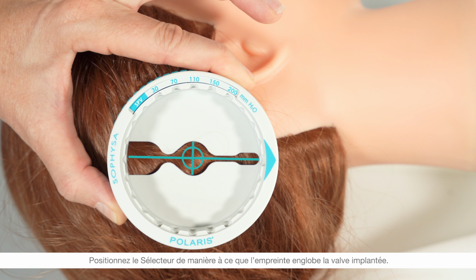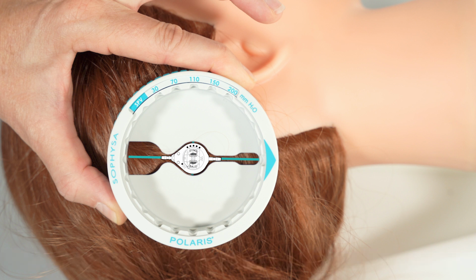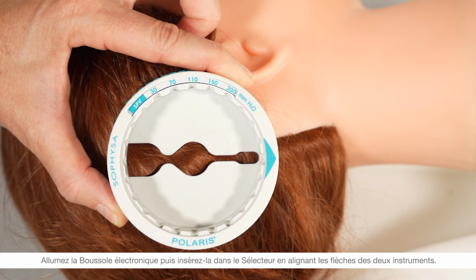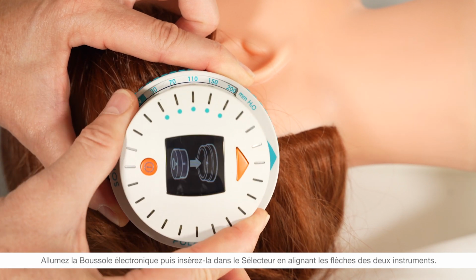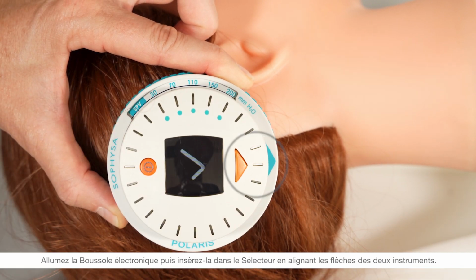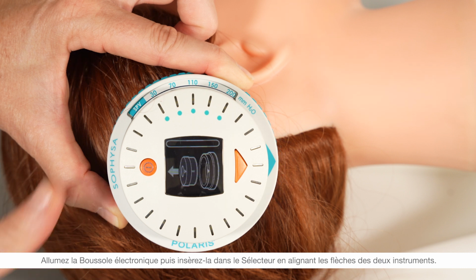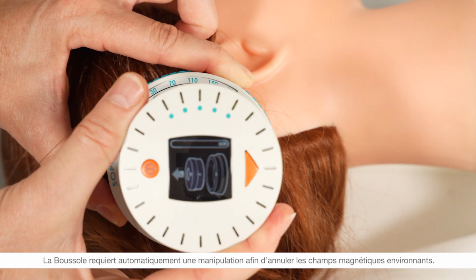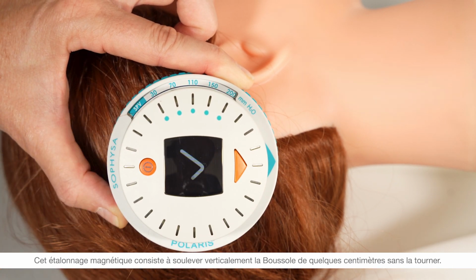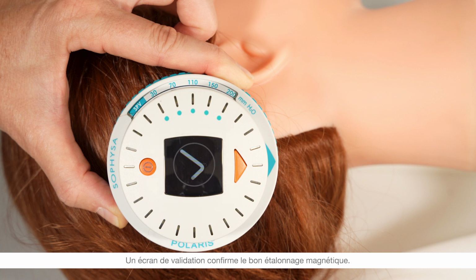Then, place the locator above the valve with its central cutout axis aligned with the valve connectors and with the arrow of the locator pointing in the direction of the CSF flow. Power on the electronic compass and insert it into the locator, aligning the arrows of both instruments. The compass will require a magnetic calibration to be performed by slightly lifting the compass and reinserting it into the locator. The screen will automatically confirm the calibration and the adjustment can proceed.